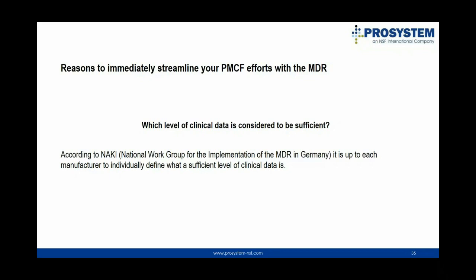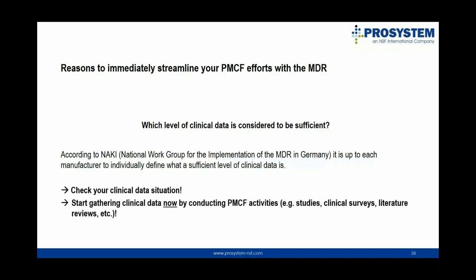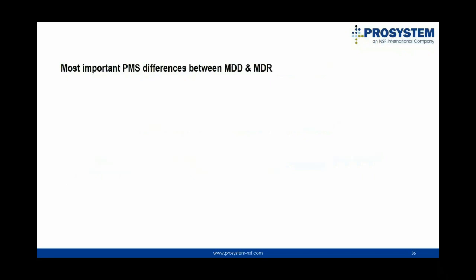According to the National Work Group for the Implementation of the MDR in Germany, the NAKI, it is up to each manufacturer to individually define what a sufficient level of clinical data is. Therefore, check your clinical data situation. Ask yourself, were the clinical investigations or PMCF studies conducted according to good clinical and scientific practice? Notified bodies are more and more challenging manufacturers' clinical evidence. The data accepted under the current MDD may no longer be acceptable under the MDR.